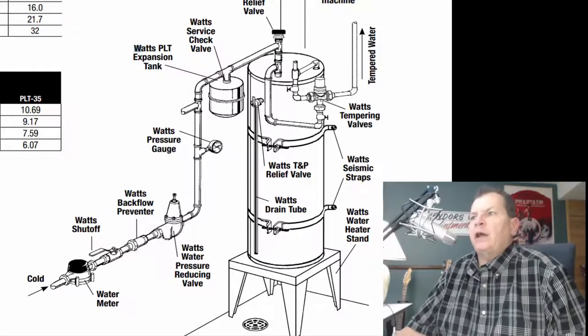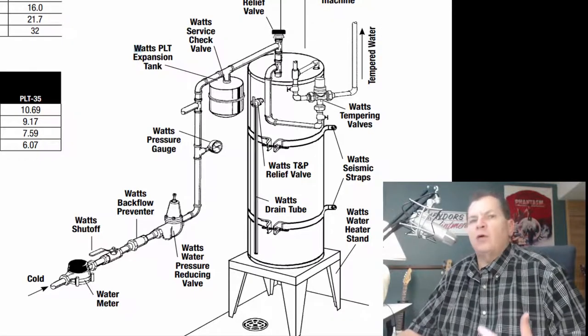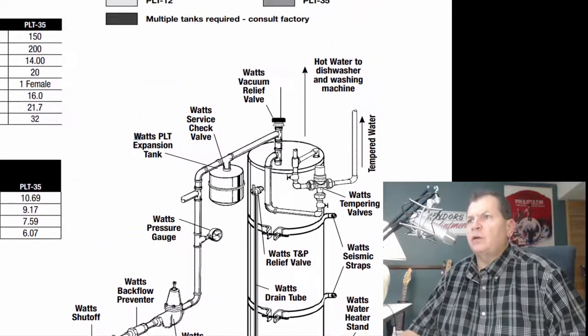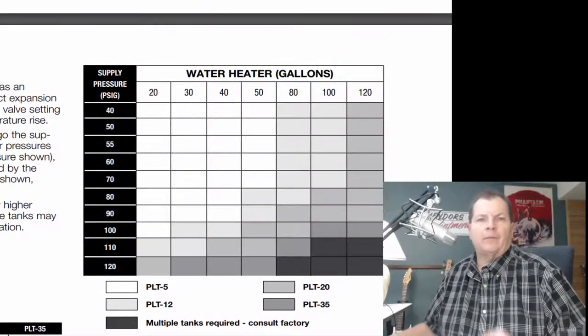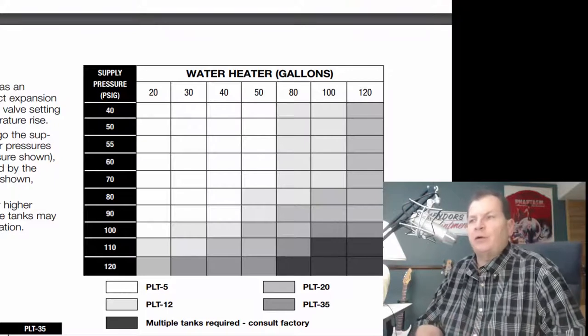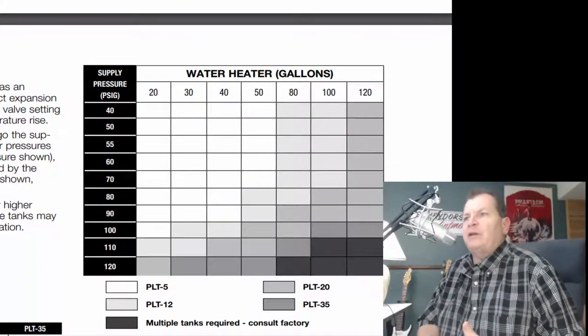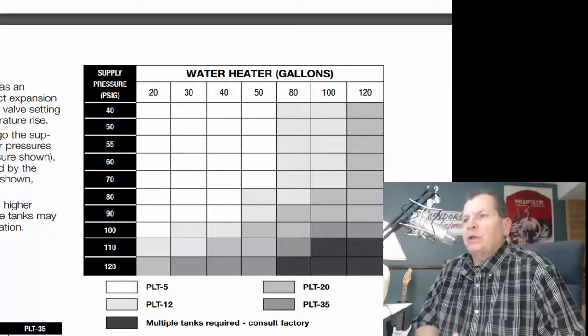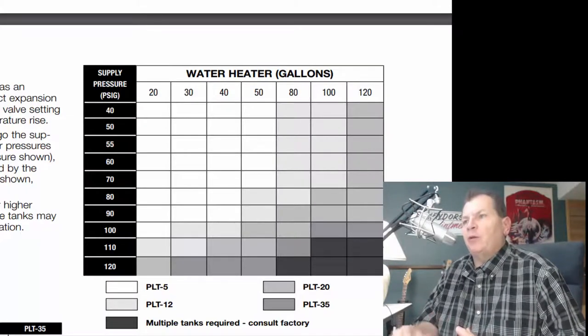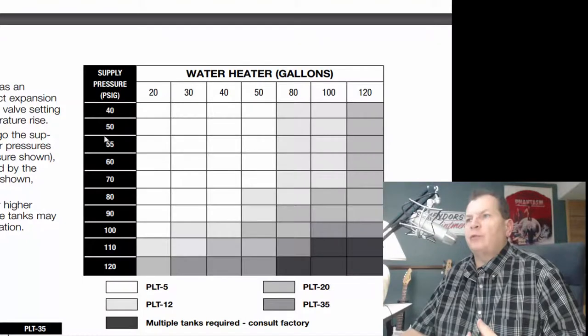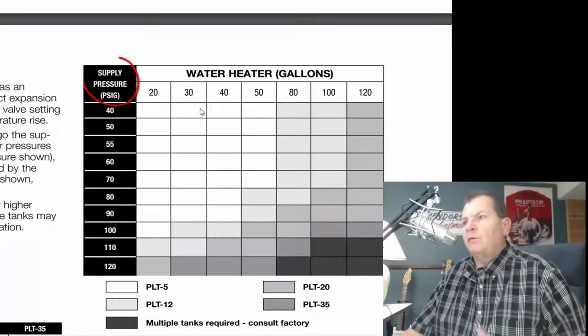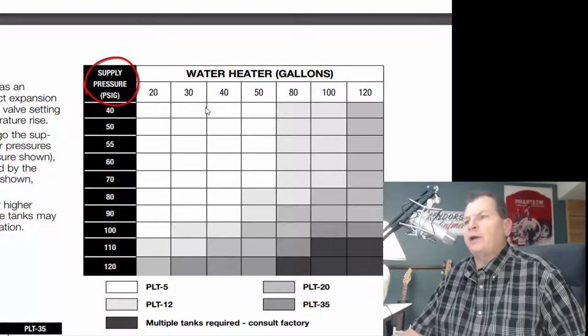So here let's go to our handy-dandy screen. So you know what expansion tank you're supposed to have. For sizing. For a domestic system, and when I'm talking domestic system, that means you're drinking water. That's your domestic. It's supposed to be whatever your supply pressure is at. That's the incoming pressure from your water main versus the size of your water heater.